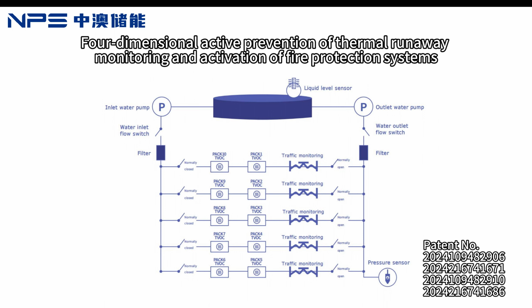When the battery is deflated, the TVOC monitoring probe will immediately detect the gas composition and synchronize monitoring of gas inflow and discharge of the adjacent battery box. The TVOC alarm triggers at the same time the gas flow of the deflated fumes triggers the gas flow meter on the pipeline, further confirming the thermal runaway deflated state of the battery.